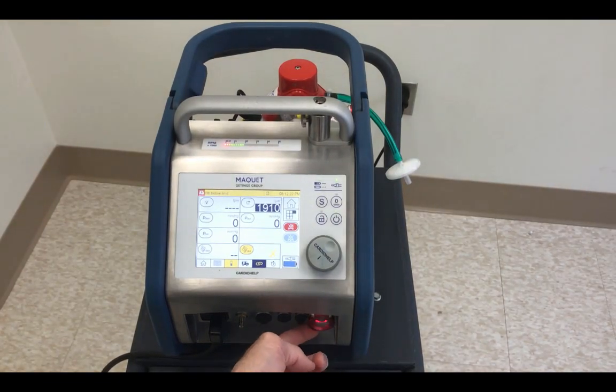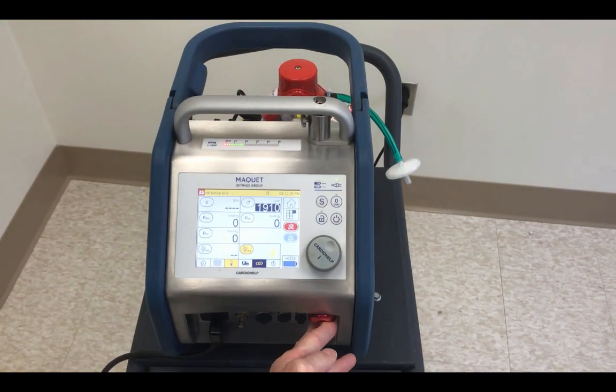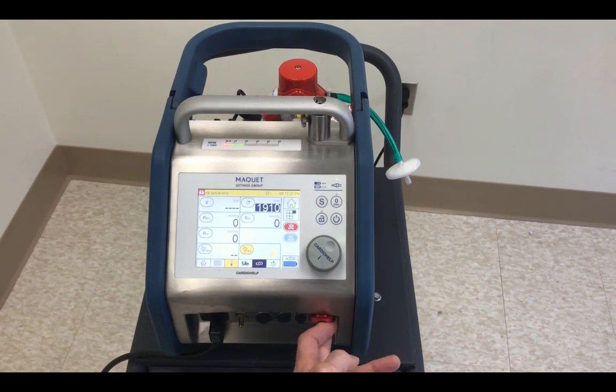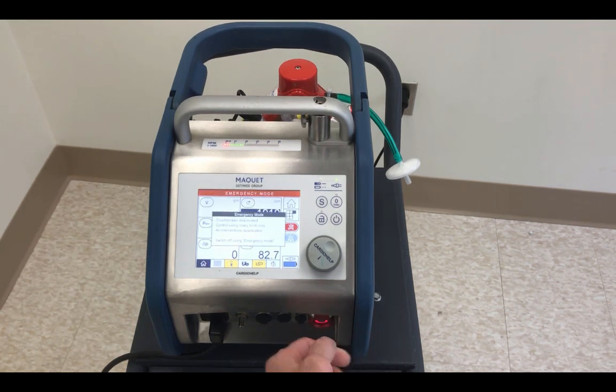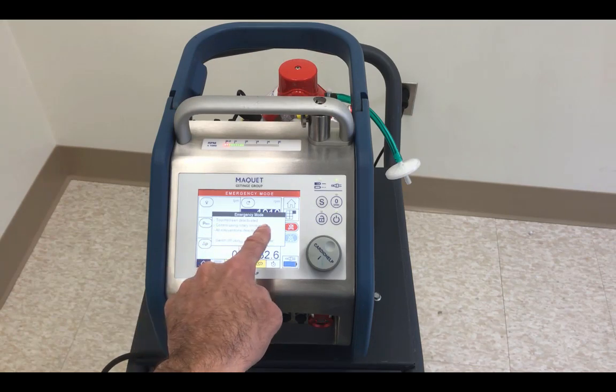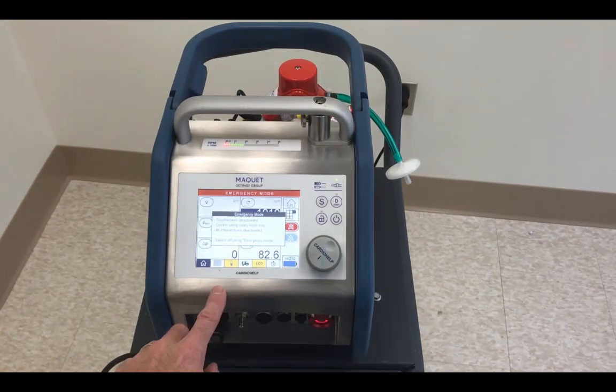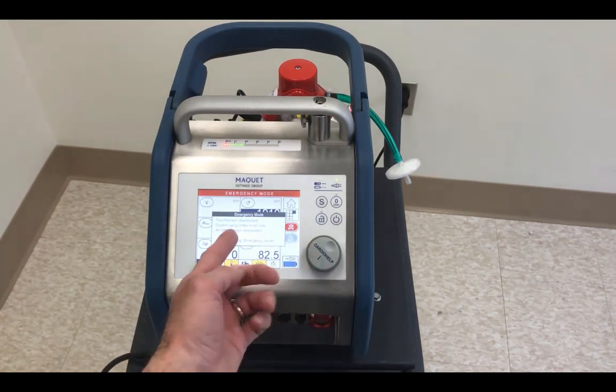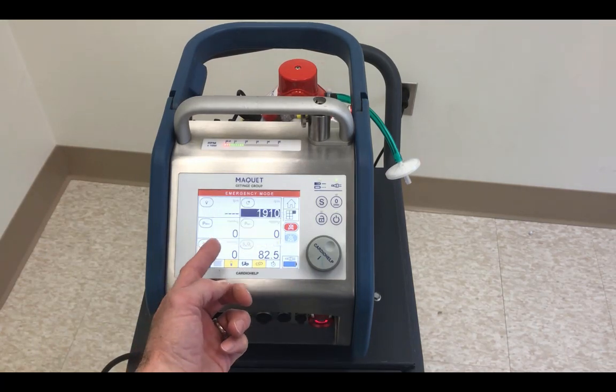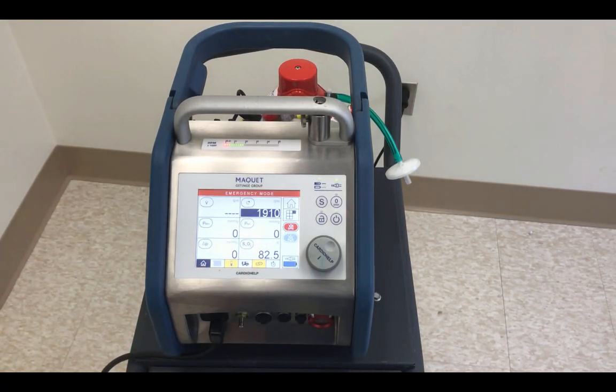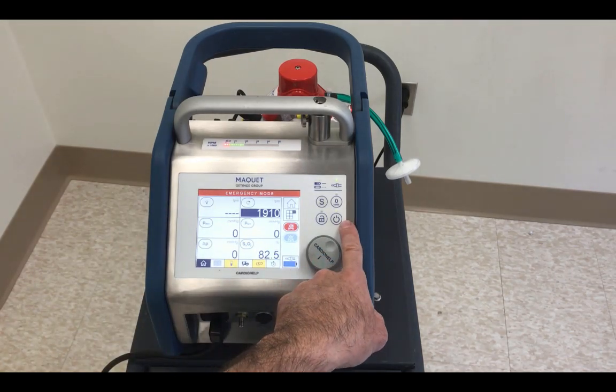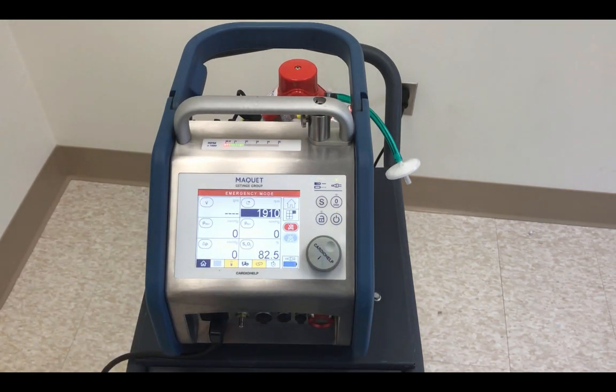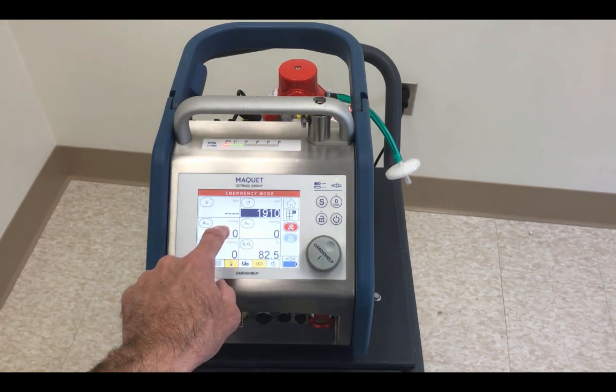In fact, let's do that. I'm going to lift the gate, and push the button, and listen for the alarms. Now if I release it, you're in emergency mode. Touchscreen is deactivated. Control using the rotary knob only. All interventions are deactivated. Switch off. The only way to get out of this is to power the pump off now. So this is not something you want to do unless you actually break this screen.